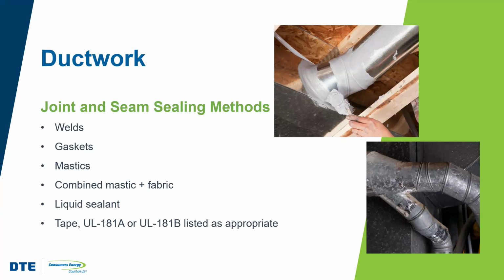the ductwork. But over the years, field reports and research, particularly some research coming out of Lawrence Berkeley National Labs, began to reveal that this tape really wasn't all that reliable for ductwork, particularly under temperature variations because it could become brittle, could simply fail, or even catch fire. So when the IRC, the International Residential Code, was developed in 2000, it prohibited its use for sealing ducts.